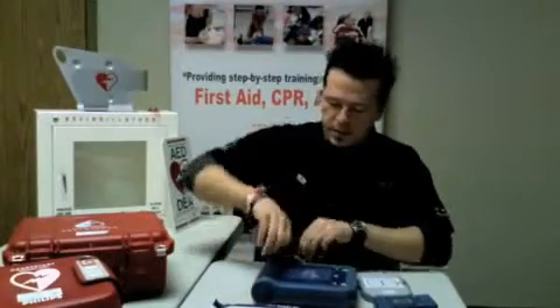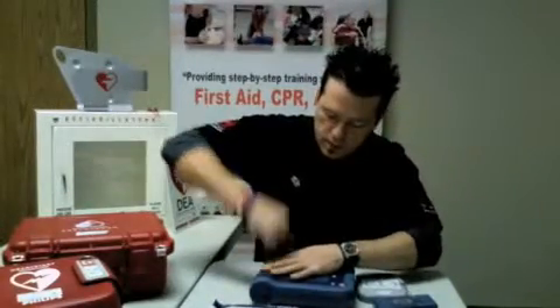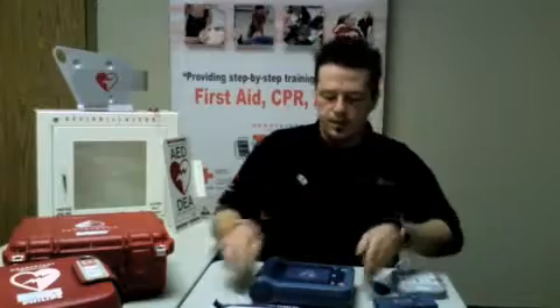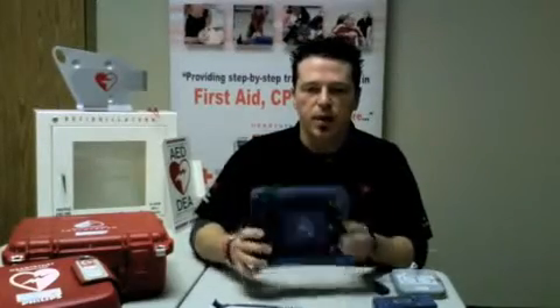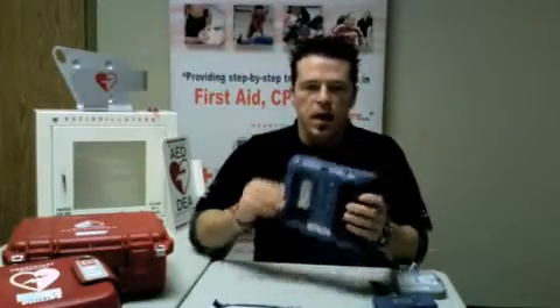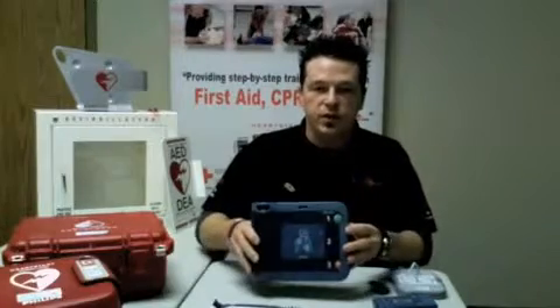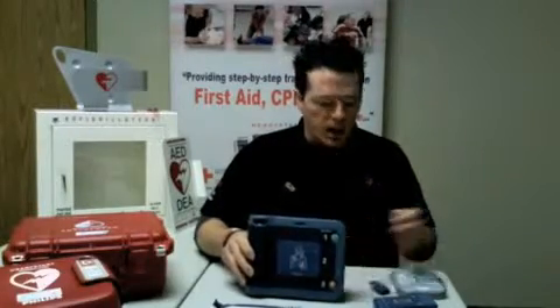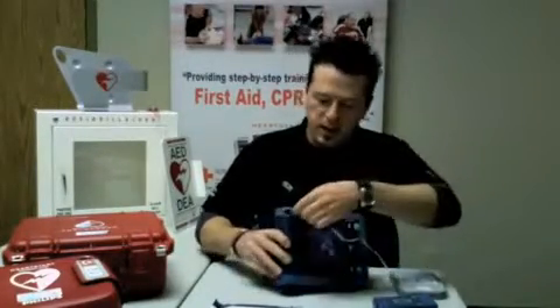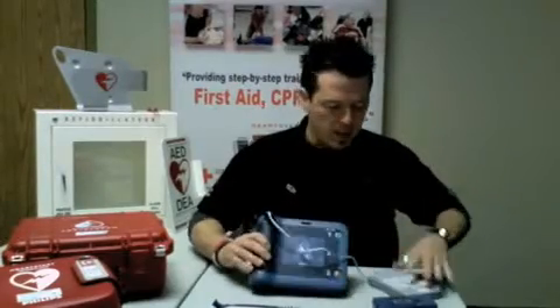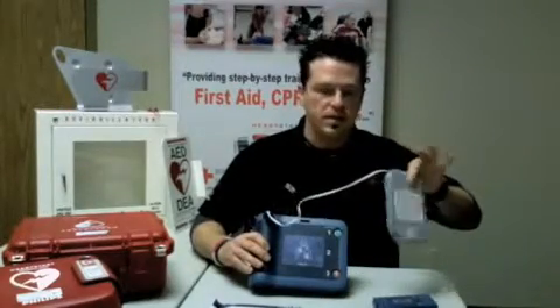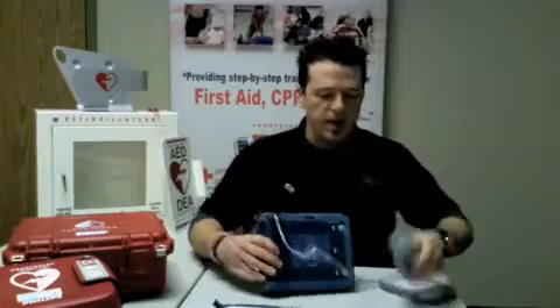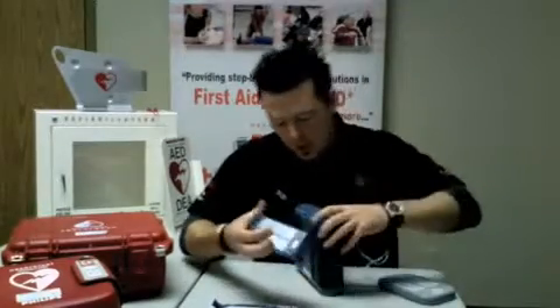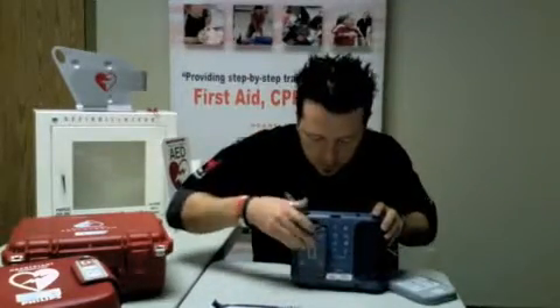And the second thing will be to unplug the electrode pads. Again, everything that needs to be taken apart has been done. Now, to do the diagnostic test and to initiate the diagnostic test, it would be to re-plug in the electrode pads, making sure to not open up this little cartridge, and to take the battery and put it back in. Clip it in.